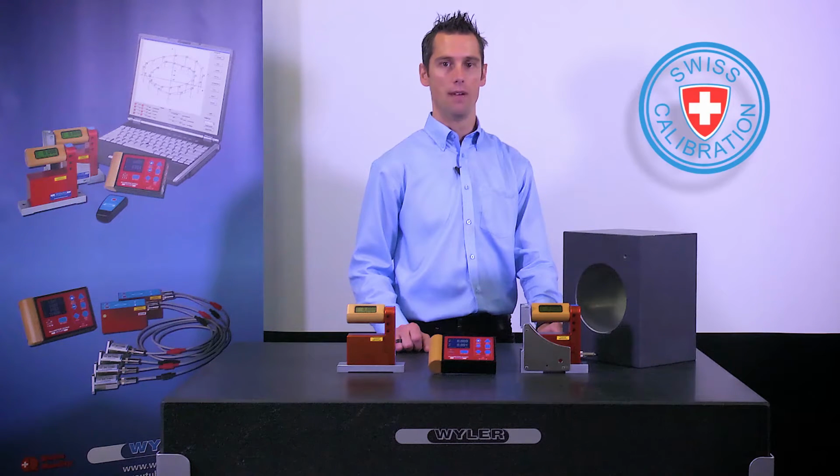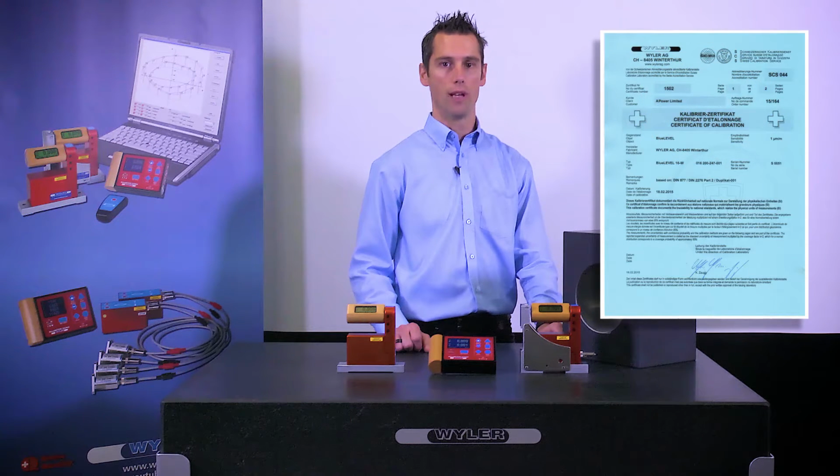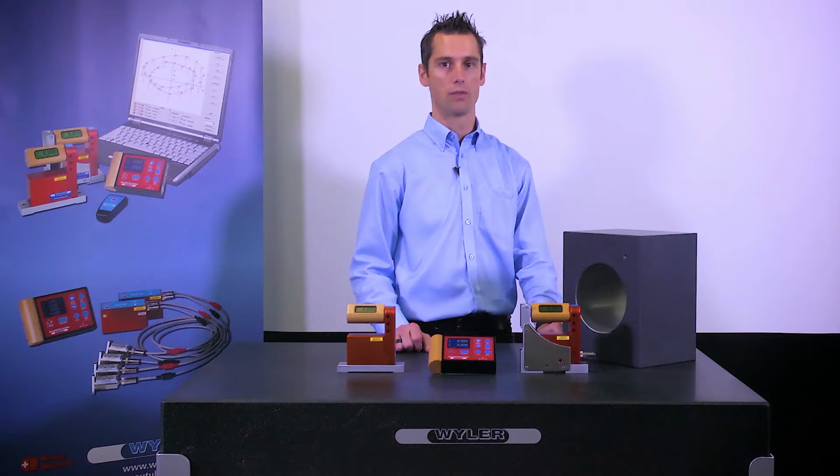For a new instrument being used at 20 degrees Celsius, or 68 degrees Fahrenheit, and for which a long-form certificate has been established, the angular error can be taken out of the certificate and can be entered in the software as a correction value. If the instrument is not new or is used at temperatures other than 20 degrees Celsius, the correct value has to be determined by a measurement.